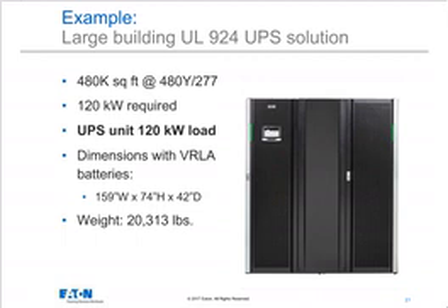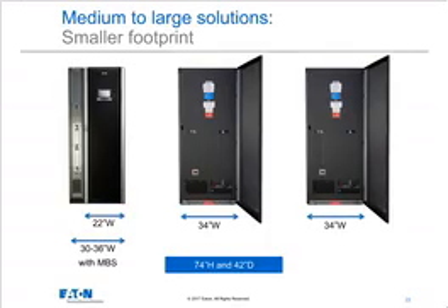Okay. So this shows a picture of a medium to large solution and the 34-inch wide battery cabinets that go with it to give the 90 minutes of battery backup time. So this shows you what part of the system is electronics, i.e. the black box on the left, and the two other cabinets there are battery cabinets, and you see they're each 34 inches wide. And by the way, each one weighs about 3,300 pounds, and it would not be uncommon to see up to 4 cabinets on there.